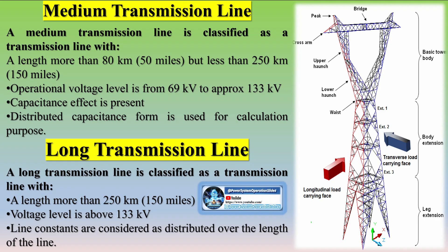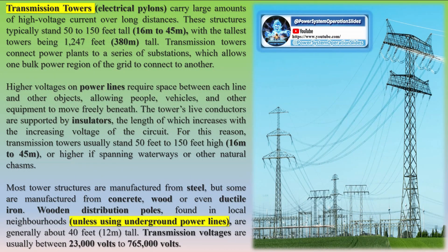A medium transmission line is classified as a transmission line with a length more than 80 kilometers or 50 miles but less than 250 kilometers or 150 miles. The operational voltage level is from 69 kV to approximately 133 kV. Capacitance effect is present, and distributed capacitance form is used for calculation purposes.